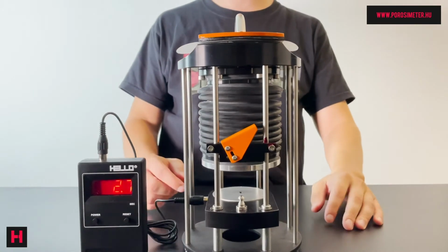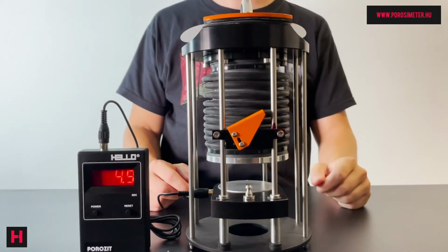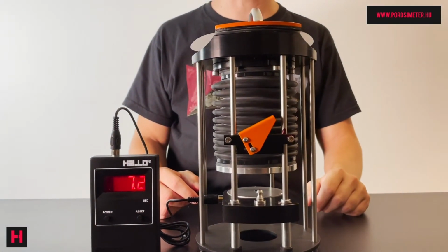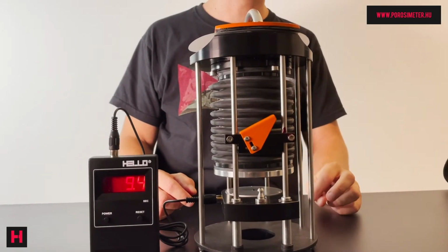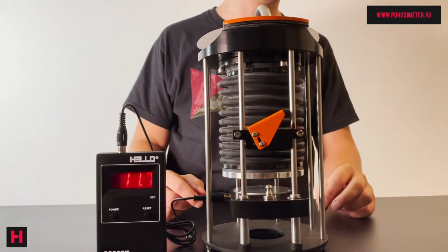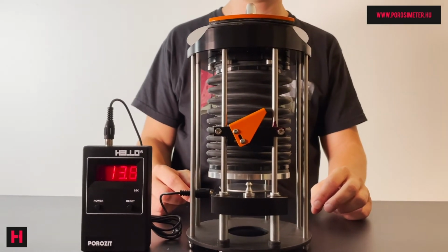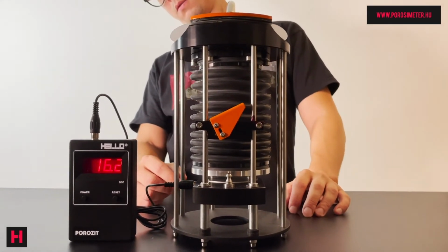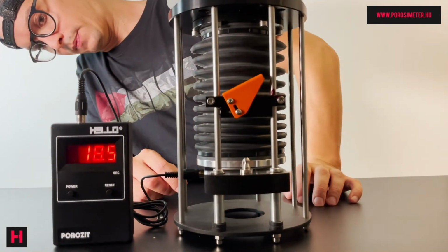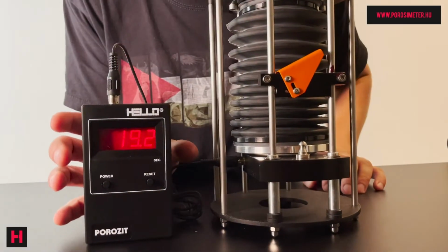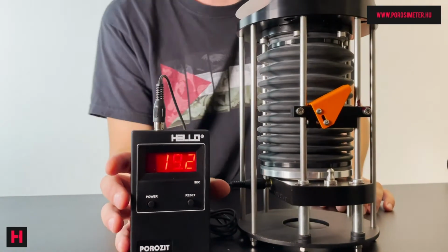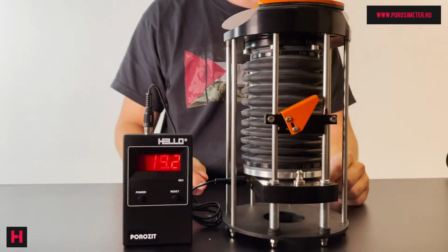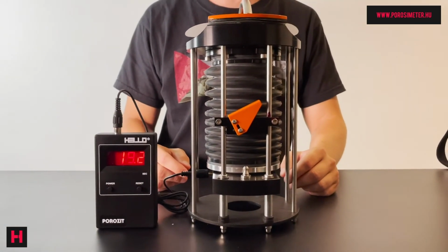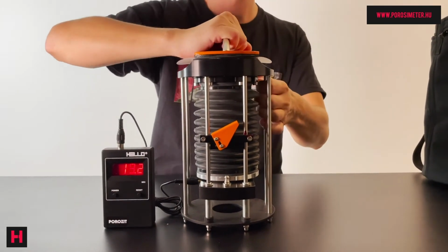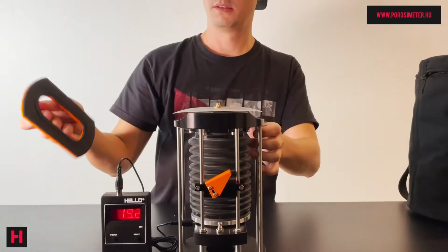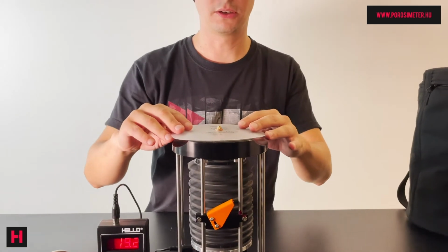So it has to be between 20 and 18.8 seconds. Let's wait a little bit. We're almost there. And the result is 19.2, which is totally perfect. The difference is 0.2 seconds, which is 1% or less. And we can pack the Porozit back.